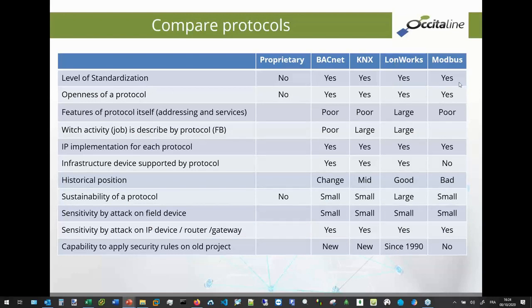And for protecting the BACnet layer on IP, or BACnet or LON or Modbus, whatever you want, it's very, very important that the IP infrastructure devices have a real router or switch with security functionality inside. It is because I spoke about the OX brass at the beginning of the presentation.